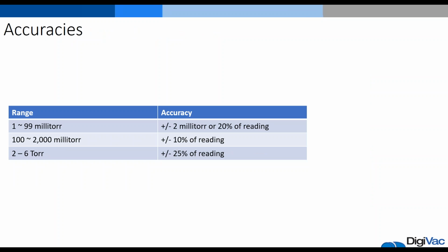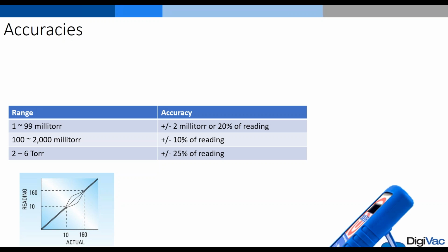So the accuracies of the gauge are, in the range of 1 to 99 millitorr, plus or minus 2 millitorr, or 20% of the reading. From 100 to 2,000 millitorr, you can get an accuracy of plus or minus 10% of the reading. And from 2 to 6 torr, you have plus or minus 25% of the reading. So to visually display the accuracies along a graph, you can see where the accuracies run consistently up to 10 millitorr. They split apart and gain different ranges between 10 and 160 millitorr, and then they come back and run in a straight line again after 160 millitorr.